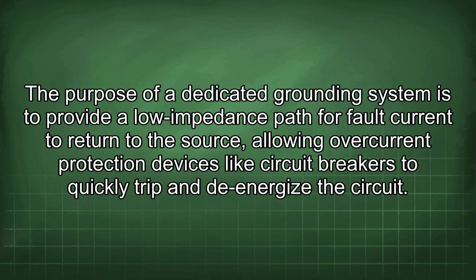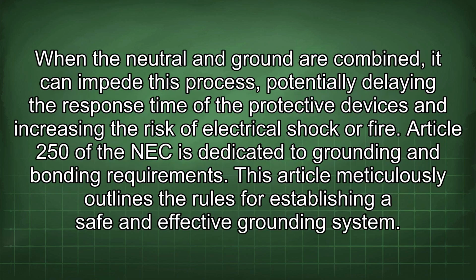The purpose of a dedicated grounding system is to provide a low impedance path for fault current to return to the source, allowing overcurrent protection devices like circuit breakers to quickly trip and de-energize the circuit. When the neutral and ground are combined, it can impede this process, potentially delaying the response time of the protective devices and increasing the risk of electrical shock or fire.